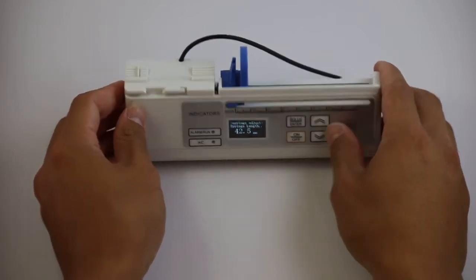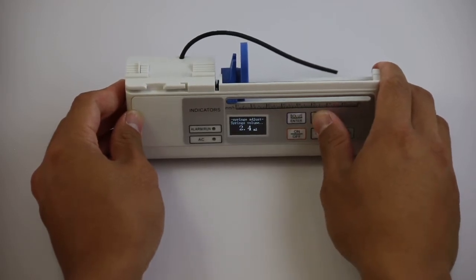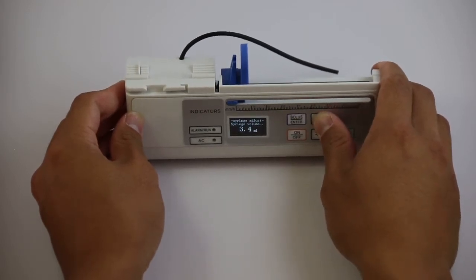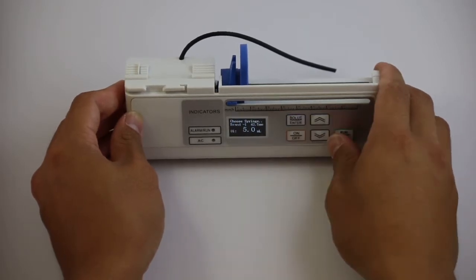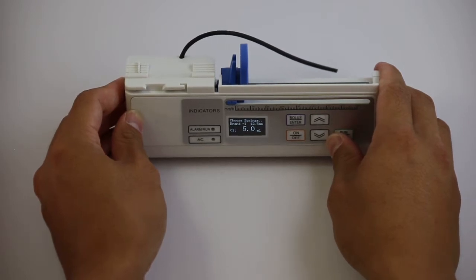Click bolus enter again, at which point you would need to set the syringe effective volume. Please refer to the volume of the syringe that corresponds to the length of the syringe measured in the previous step. Once you've completed this, click enter again to finish the syringe calibration.